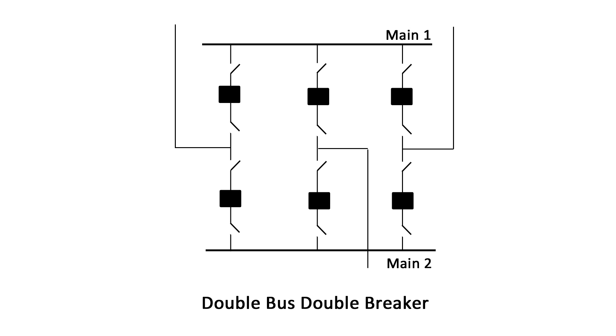Substations with a double bus, double breaker arrangement require twice the equipment as the single bus scheme, but are highly reliable. This scheme is typically found in high-voltage transmission substations or generating stations.